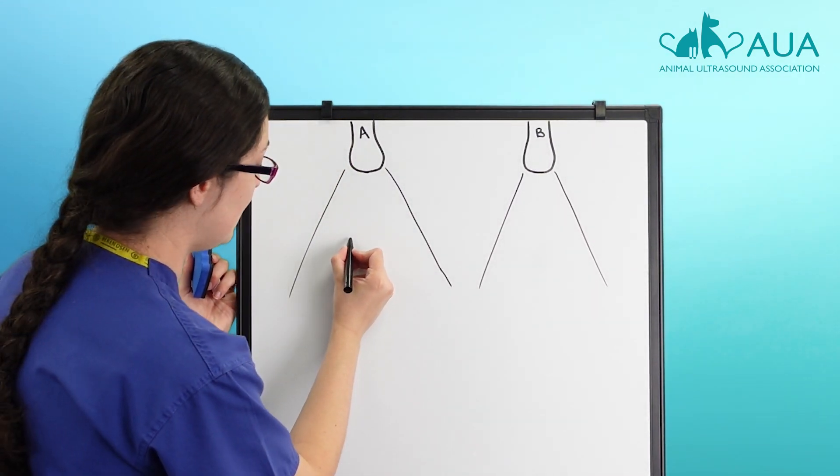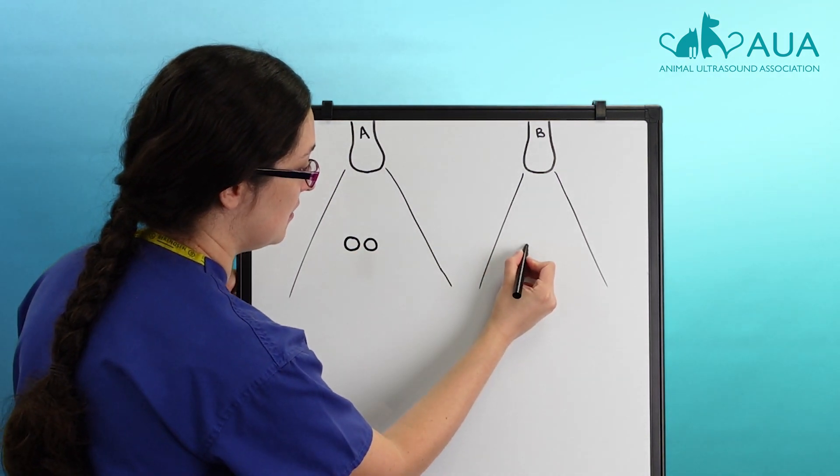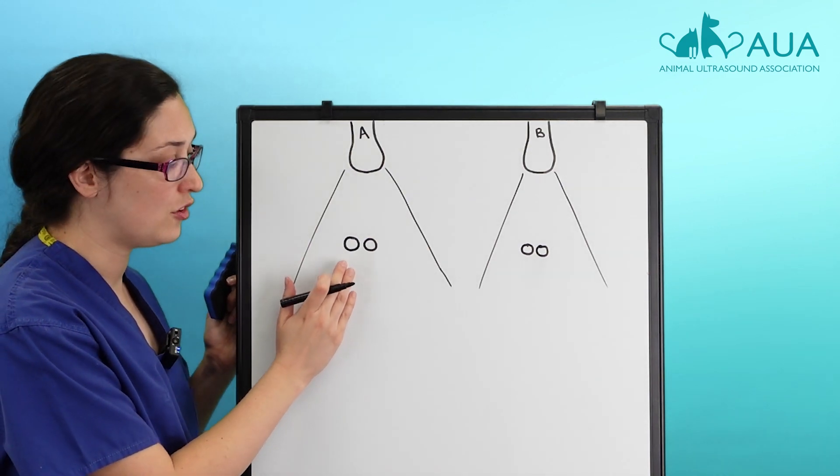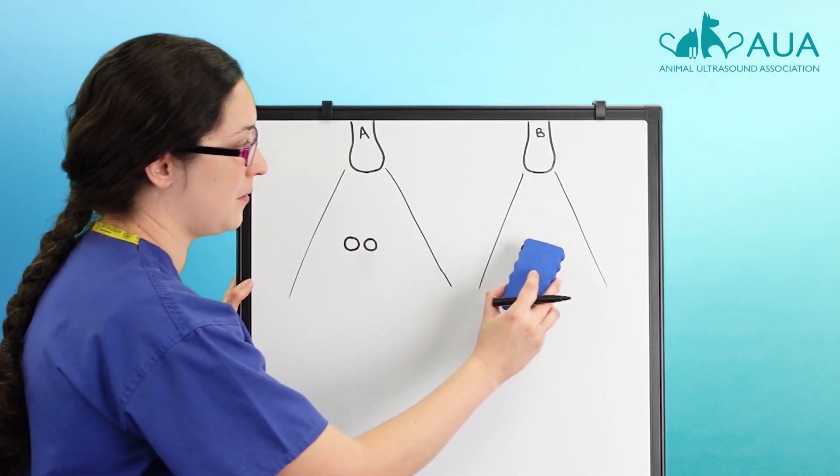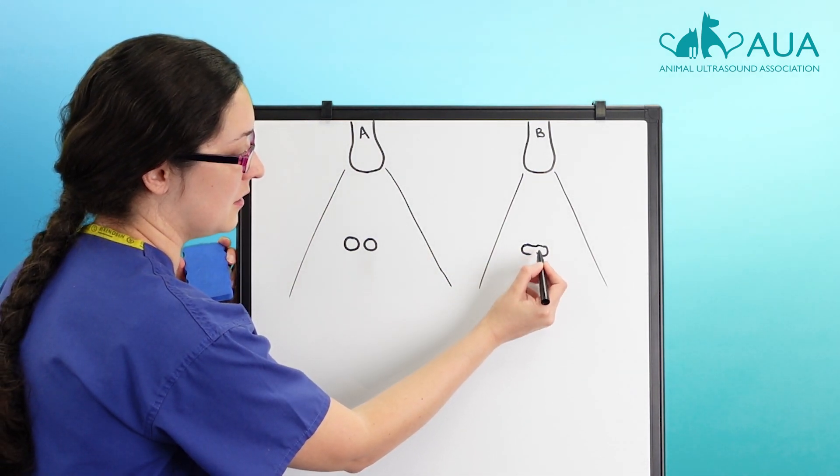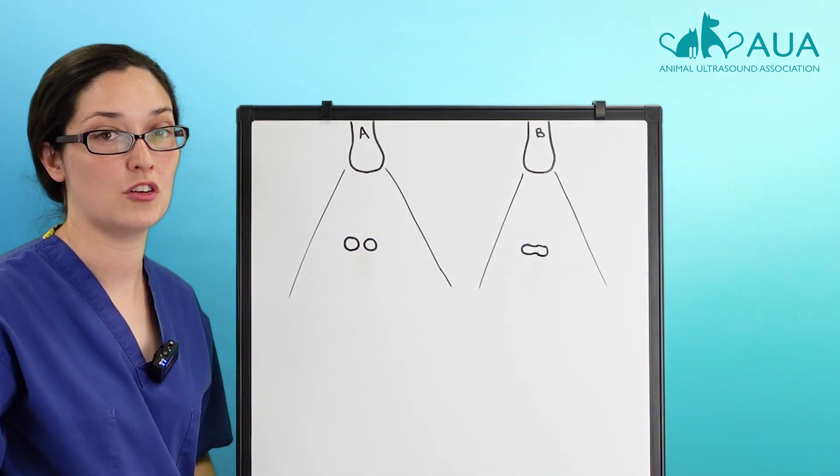Now lateral resolution is the exact same thing, but in the horizontal direction. So again, scanner A has good lateral resolution, these two points are shown as two points. Scanner B has poor lateral resolution, and so you see something like this on your scanner.